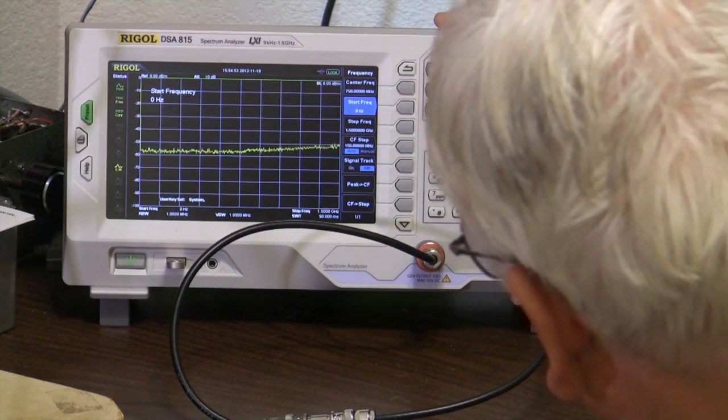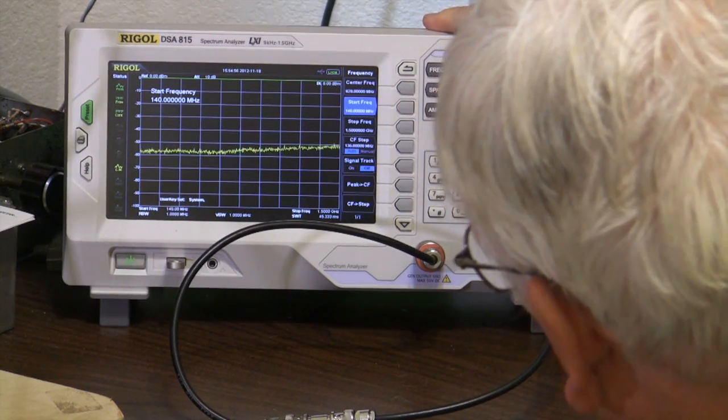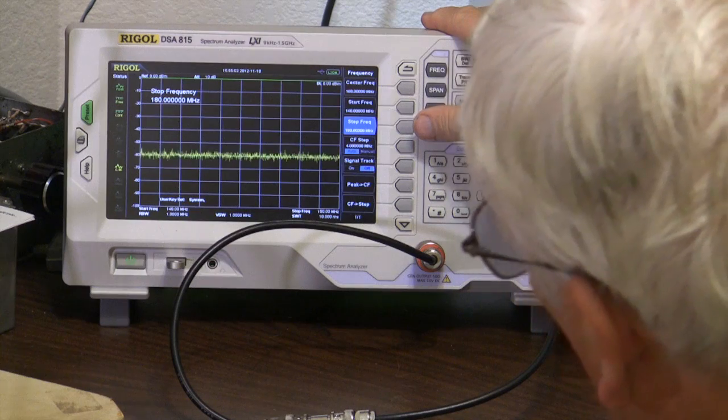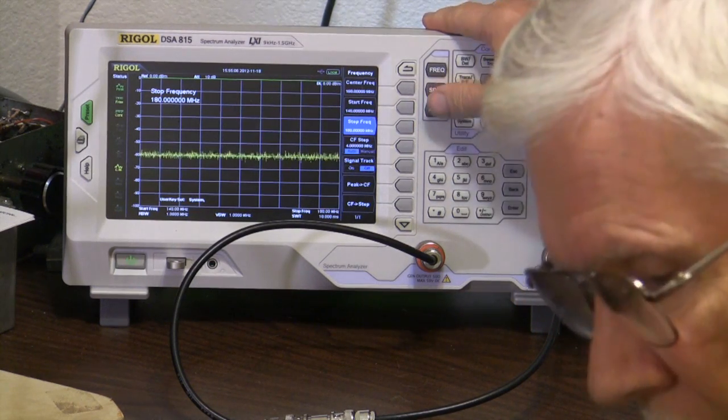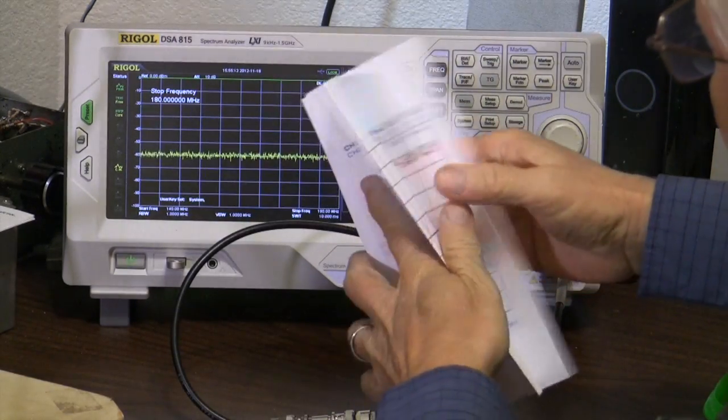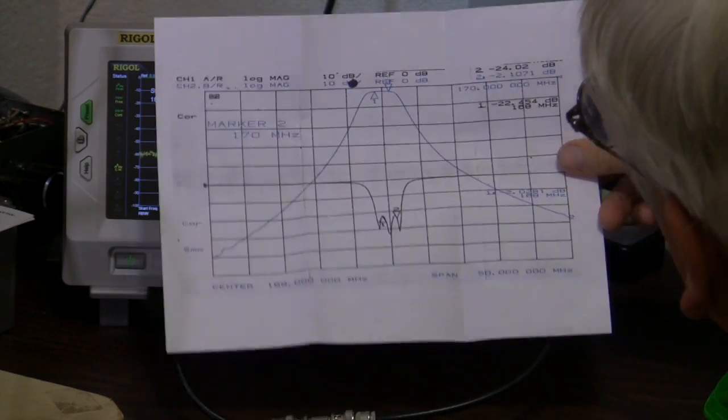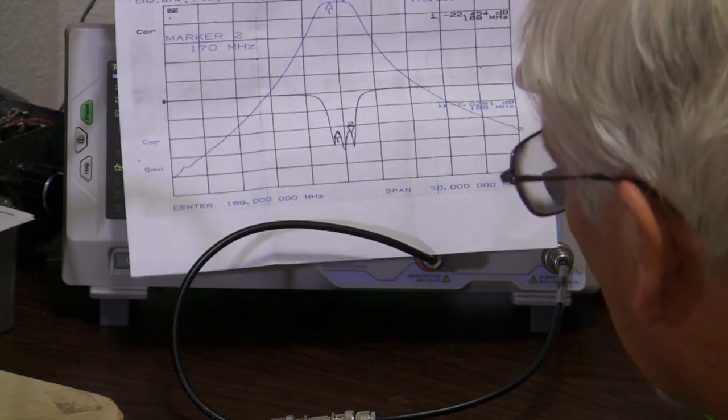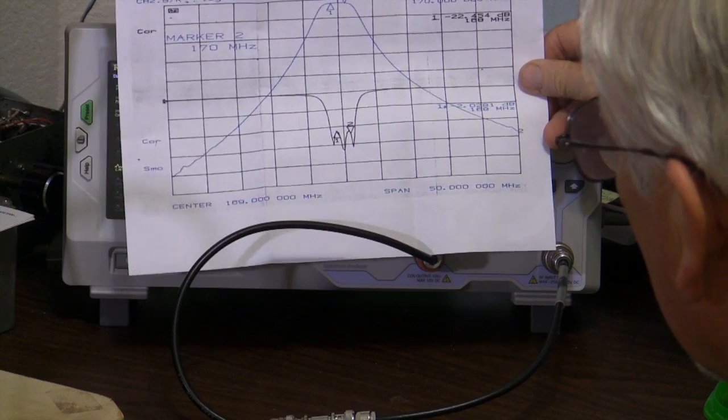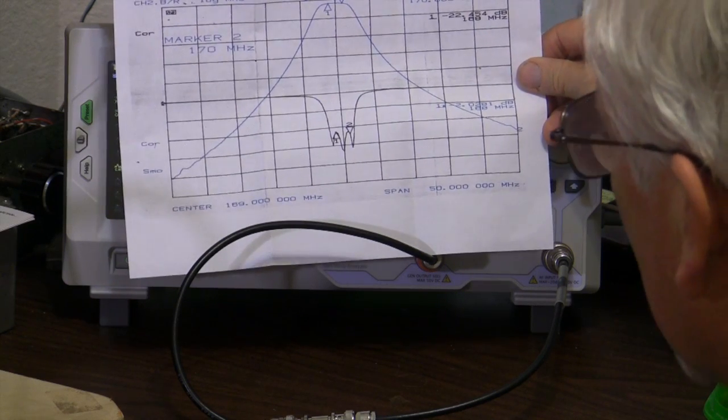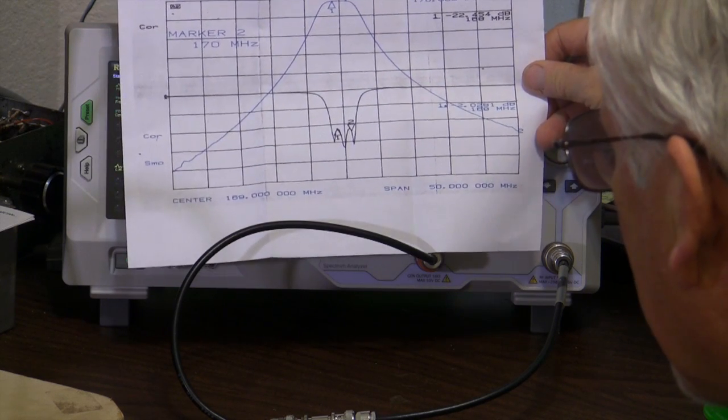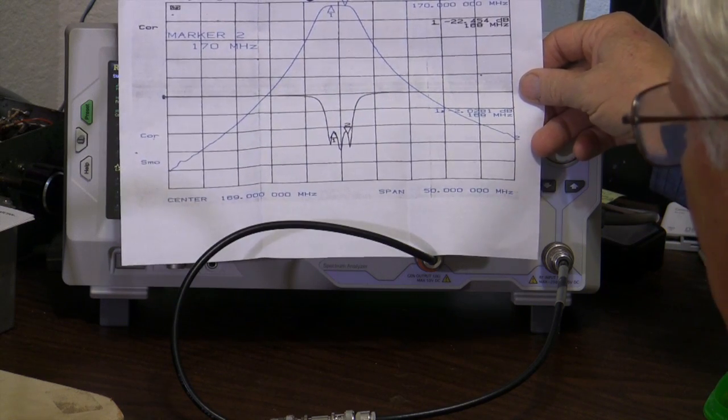So we're going to set the analyzer up to cover about 140 to 180 megahertz. So frequency here start 140 and stop 180 megahertz. However, it turns out that I have a piece of paper here that has the filter as seen on a look like HP sweep generator, or shall we say network analyzer. This is the manufacturer's drawing, or actual plot. So we're going to use this for our purposes.